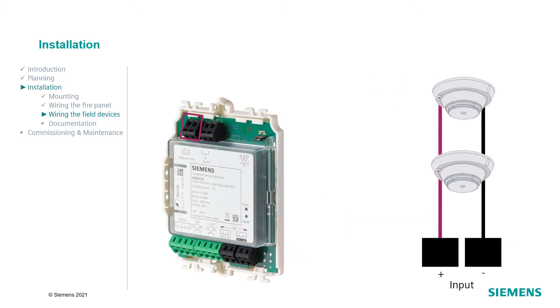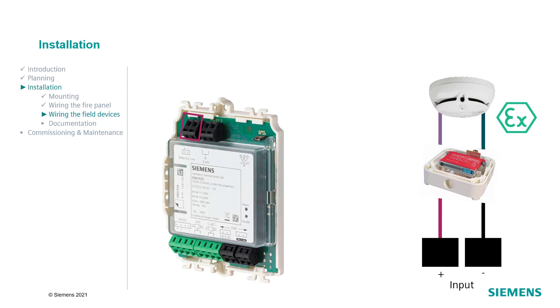The last element which we would like to show you is the FDCI723. It offers one control input and can be configured either as collective conventional detector lines or as conventional Ex detector lines with the SB3X barrier. Connect the plus and minus poles to the correct connectors of the conventional detectors or the SB3X barrier.